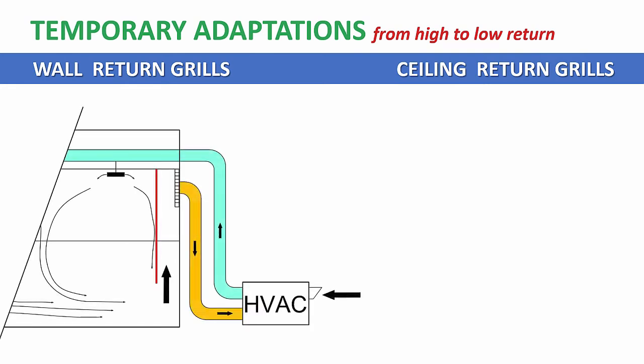For example, if we look at the wall grills, we can install a temporary partition that takes care of the return air. So with a temporary partition, we see that the pattern of the return air with bacteria and viruses is changed. The air is staying low and is going up, rising behind the temporary partition or temporary duct, and is going to the return grill. So the system remains the same, but the air pattern changes. What is better and is reducing the risk of infection.